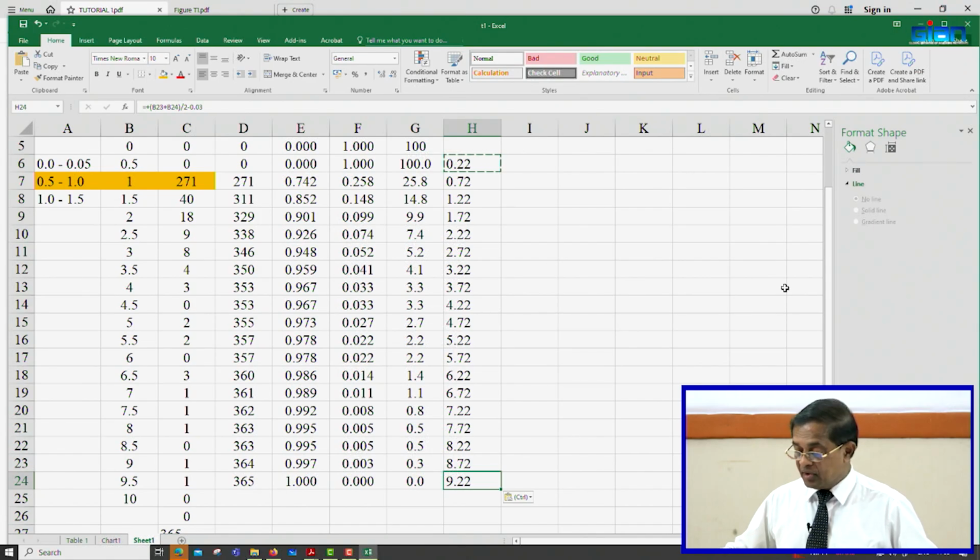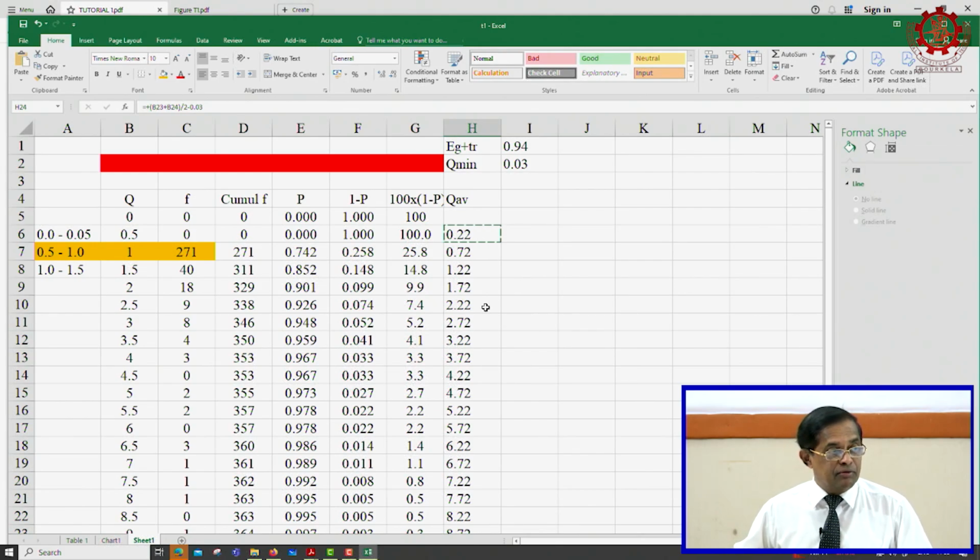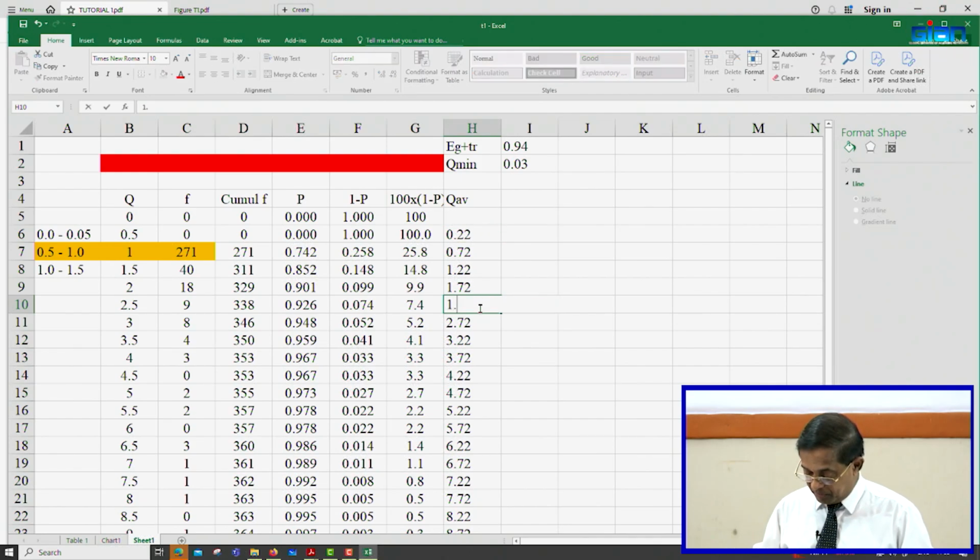Okay, right, Q available. Now, we have selected 1.8 as our rated flow. Therefore, we can lock it there. From this point onward, we can say flow available for power generation is 1.8, because we can't generate more than that, right. So, after 1.72 I will lock it to 1.8.